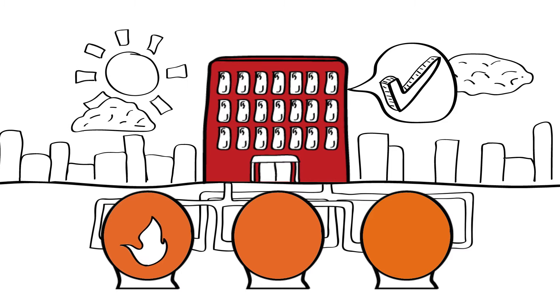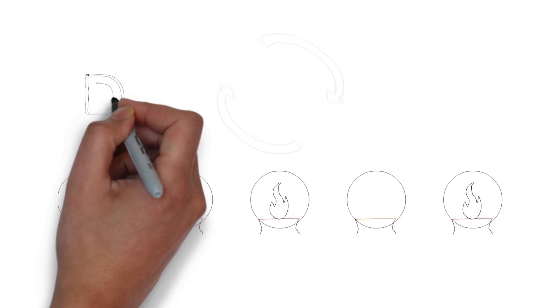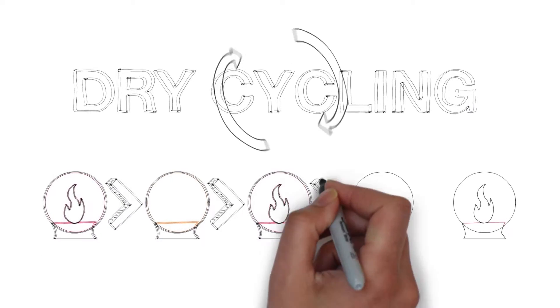As the boilers start to cool, they can fire again to keep hot even though there isn't a need for heat in the building. This is what's known as dry cycling.